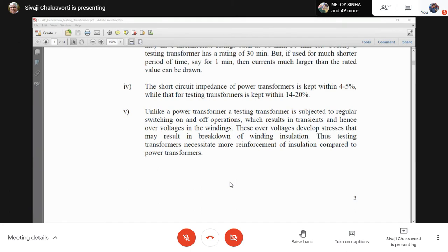To limit that, if I increase the short circuit impedance to 20%, then indirectly I can say that even if the transformer is short circuited, the current will not be higher than 5 times the rated current. It is a straightforward calculation. 20% means that. So if the rated current is, let's say, 100 ampere, the short circuit current will not cross 500 ampere. So it's an automatic limit. And this can happen in testing. An equipment under test can fail. Over the years we test so many equipment, there will be failures. So that's the reason for the very big difference in the short circuit impedance of a power transformer and a testing transformer. This again makes a lot of difference in the design of the transformer.